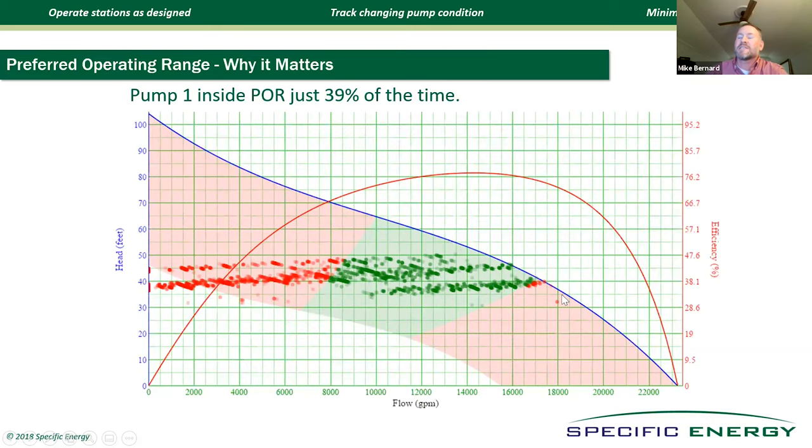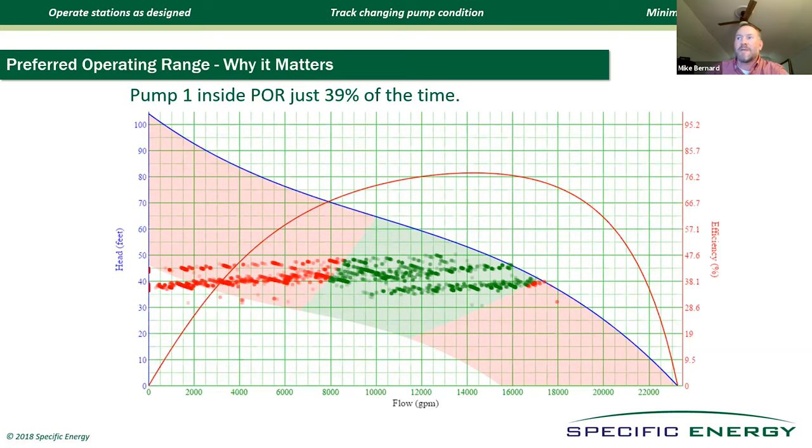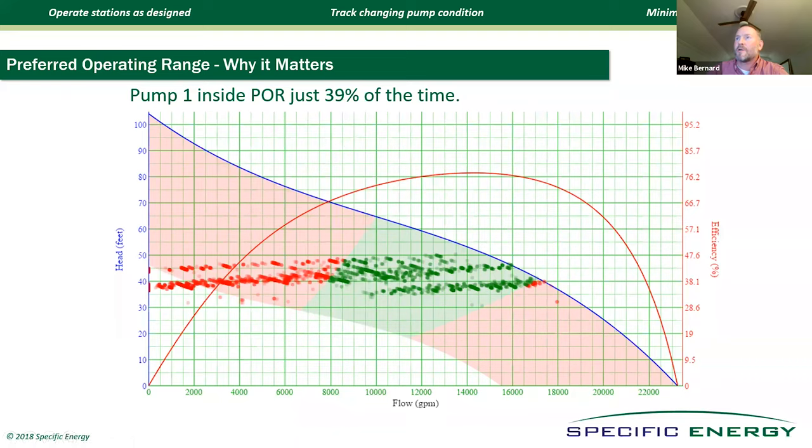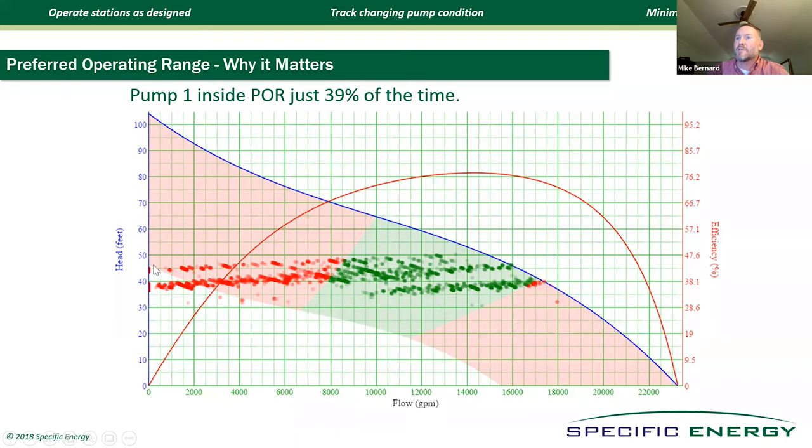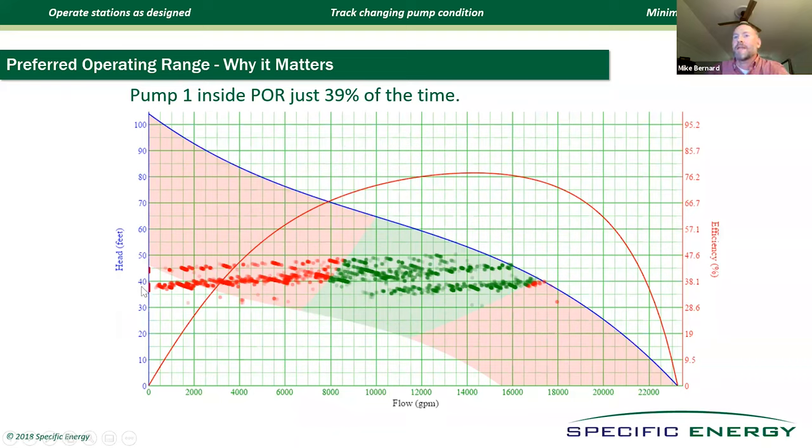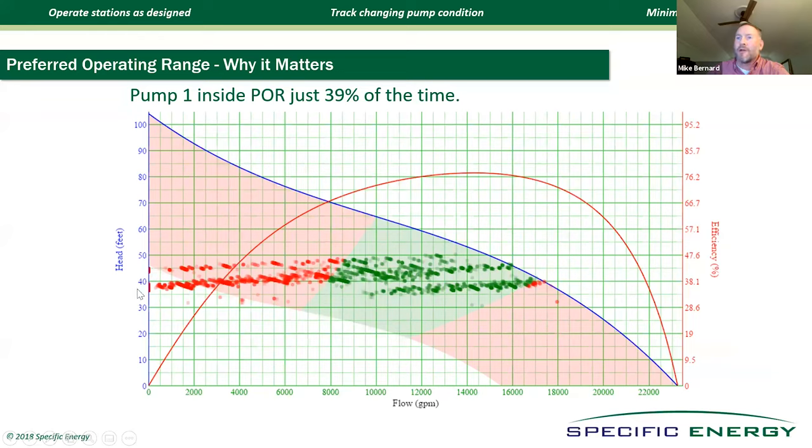That's part of what we bring. And unfortunately, this is the rule and not the exception. This is a big pump station in the Houston area. It's got four constant speed pumps and two variable frequency drive pumps. Unfortunately, these VFD driven pumps in this case are operated inside the preferred operating zone just 39% of the time. This is what they were doing before they had our software. The issue is that they just simply slow these VFDs down too much. What you can't tell is that 15% of the data points are stacked up here at what we would call the shutoff head, where the pump is consuming energy and producing head, but it's not enough to overcome the static. So these pumps are deadheaded.